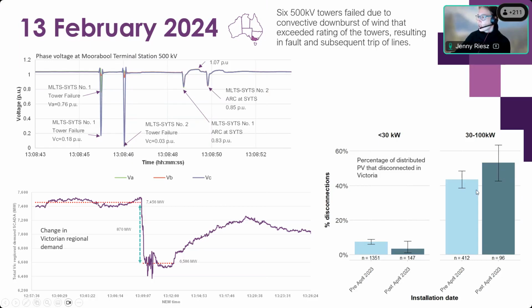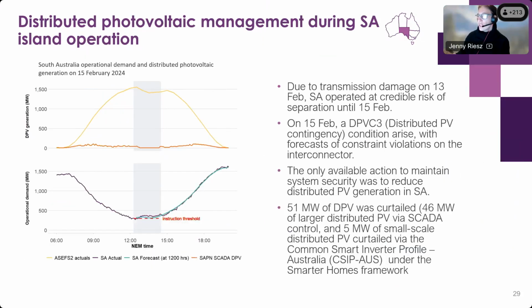This is showing you again the distributed PV disconnection rates. For the smaller systems, a moderate amount of PV disconnected from the older systems. These are the newer systems, which you can see have improved in their behaviours with the new 2020 standard becoming in and improving compliance with that. These are the larger systems, which I flagged before. We're consistently seeing those higher disconnection rates from them. So a lot of work to understand all of this so that it can feed into our power system models and represent these behaviours accurately. One of the most interesting elements of this event was looking at the subsequent operation after that event.